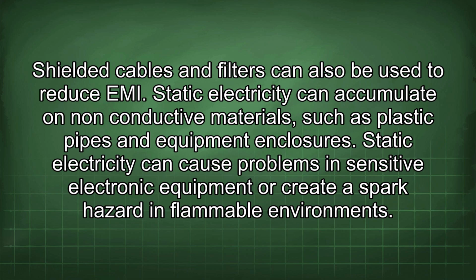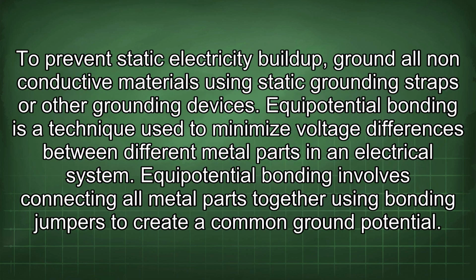Static electricity can accumulate on non-conductive materials, such as plastic pipes and equipment enclosures. Static electricity can cause problems in sensitive electronic equipment or create a spark hazard in flammable environments. To prevent static electricity buildup, ground all non-conductive materials using static grounding straps or other grounding devices.